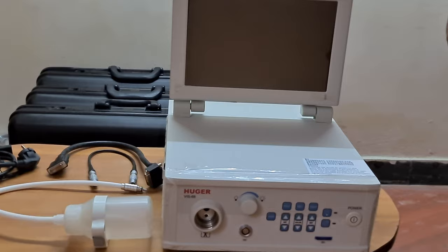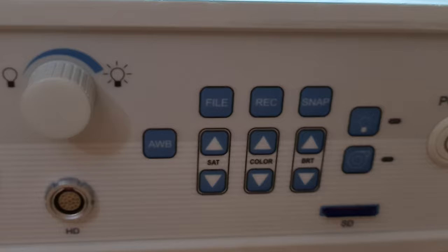Now I'll show you the front panel of the processor. There is a port where you connect the video scopes directly, and a dial to adjust the LED light source intensity. You can see the HD marking — that is the signal cable port which connects to whichever scope you are going to use. There is an automatic white balance button and a button called 'File' — when you click File after completing a procedure, a new folder gets created so each patient's data is stored separately.